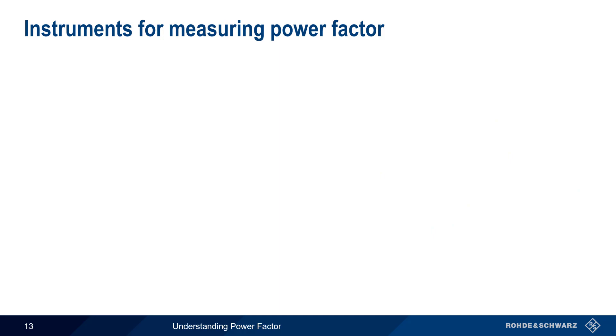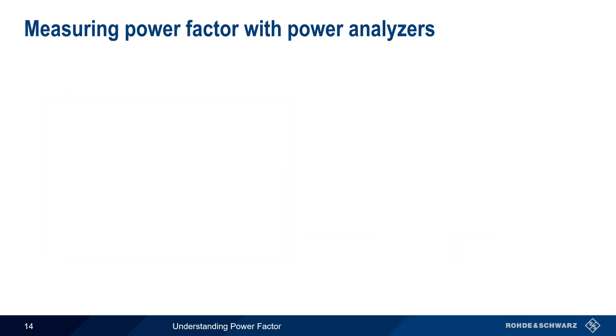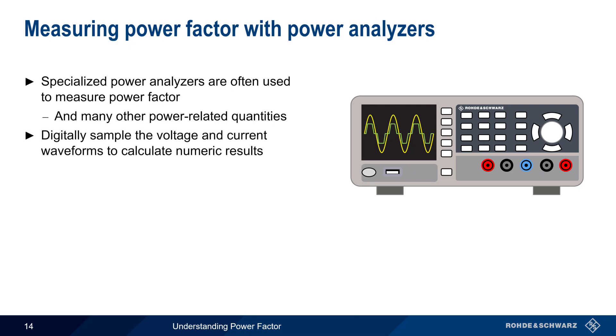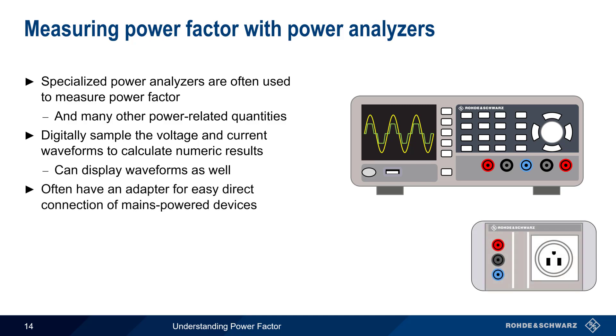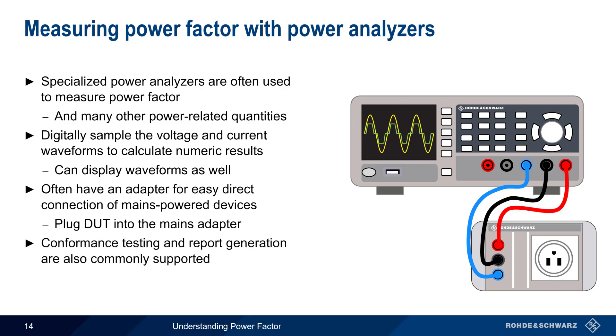Two categories of instruments are used for measuring power factor: power analyzers and oscilloscopes. As the name implies, power analyzers are specialized instruments that can be used to measure power factor as well as many other power-related quantities. These instruments digitally sample both the voltage and current waveforms in order to calculate numerical results. In most cases, power analyzers can also display the voltage and current waveforms, making it easy to visually determine whether displacement and/or distortion are occurring. Typically, a power analyzer has a special adapter for easy connection of mains-powered devices. The device under test is simply plugged into the mains adapter, which is then connected to the analyzer by a series of cables. Power analyzers also commonly support more advanced features for testing conformance to various standards, as well as generation of reports.